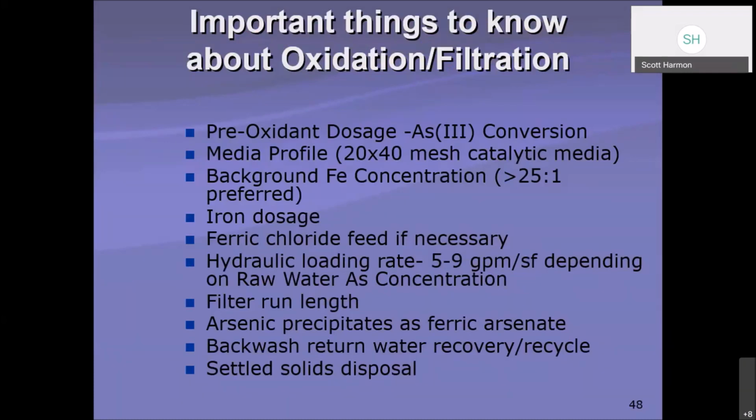Hydraulic loading rates with any facility, very important. You have to have enough time for whatever you're trying to settle out. In the case that we're talking about today, it is arsenic, and you have to have enough time for that to happen. Filter run lengths, of course, are always important no matter what you're treating for. And then the arsenic precipitates as ferric arsenate. So it's bound to the iron particle, whether it's through the natural iron in the water or the ferric that you're using as your coagulant.